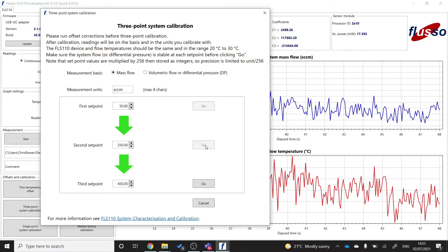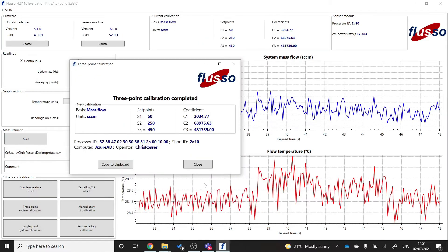And finally, I'm going to set my mass flow controller to the final set point, 450 SCCM. And once the flow has settled, I'm going to click go. And there you can see that the three point calibration has successfully completed. And you should be getting accurate and repeatable measurements from your FLS110 evaluation kit.